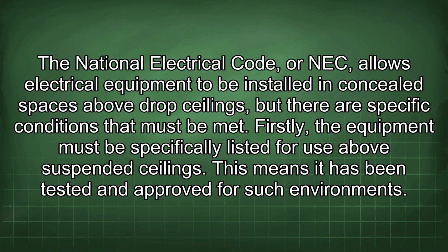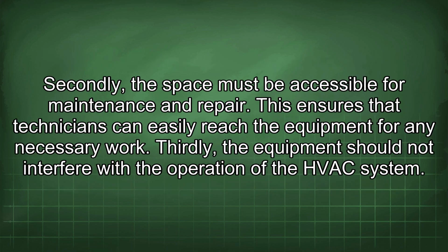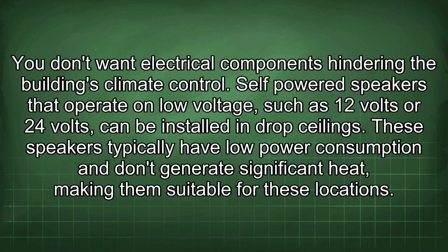The National Electrical Code, or NEC, allows electrical equipment to be installed in concealed spaces above drop ceilings, but there are specific conditions that must be met. Firstly, the equipment must be specifically listed for use above suspended ceilings. This means it has been tested and approved for such environments. Secondly, the space must be accessible for maintenance and repair. This ensures that technicians can easily reach the equipment for any necessary work. Thirdly, the equipment should not interfere with the operation of the HVAC system. You don't want electrical components hindering the building's climate control.